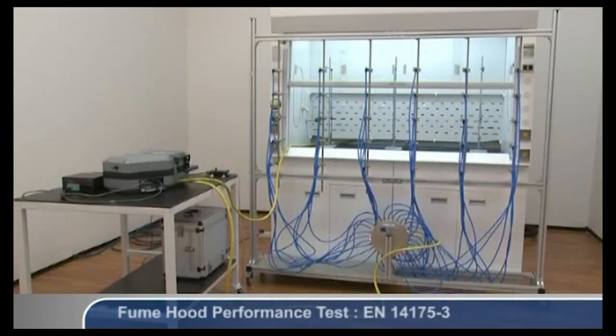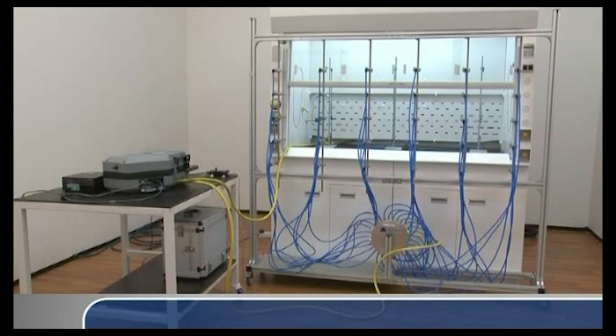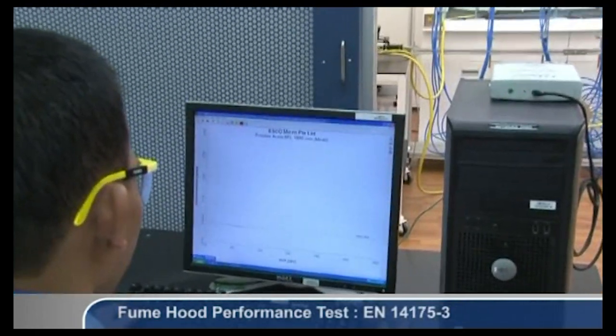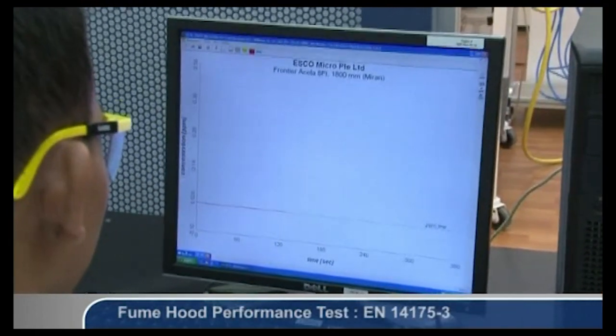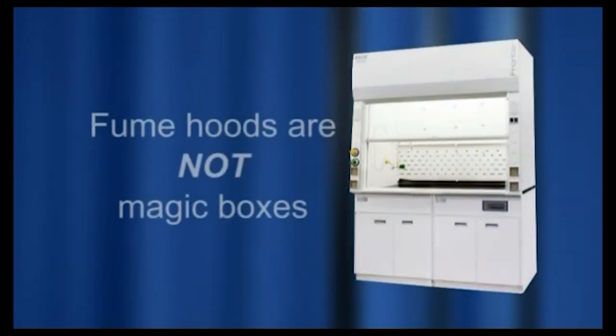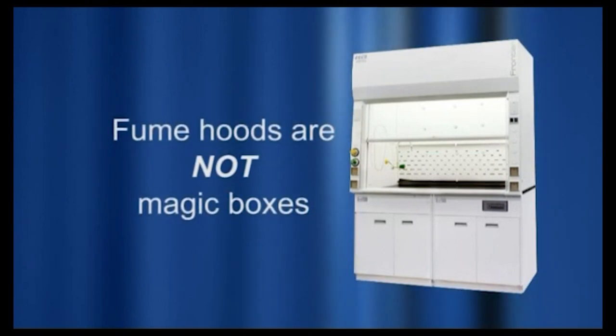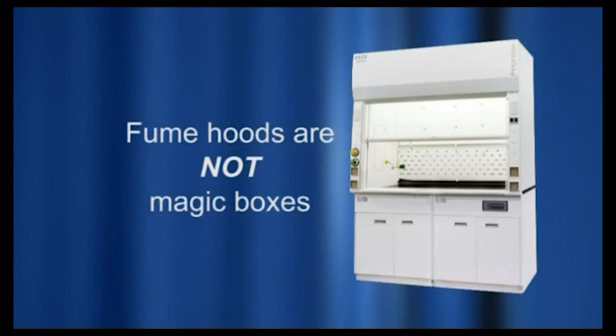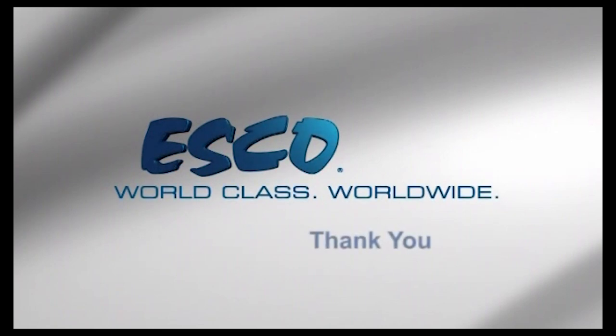In fact, these same studies have shown that approximately a third of fume hoods in use in the U.S. fail to meet the safety criteria specified in ANSI Z9.5. Laboratory exposure to chemicals is insidious, with long-term health effects that may not manifest themselves for years. Remember, fume hoods are not magic boxes — they are simply containment tools intended to augment well-executed operations. We hope you've enjoyed your training with ESCO.